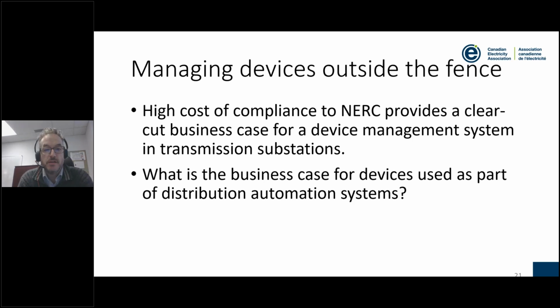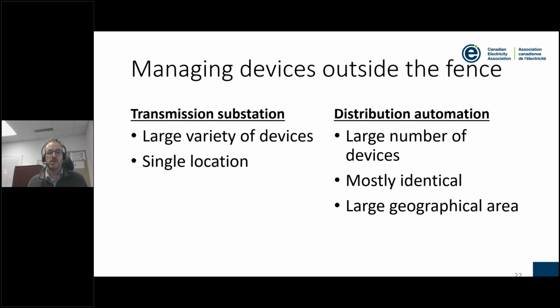Just the cost of trying to be compliant with NERC is a business case in itself for transmission substations. Typically, budgets associated with transmission substations are much higher than distribution, but is there still a business case for devices used in distribution and automation systems? Transmission substations have a large variety of devices but only a few locations, whereas distribution automation has a large number of devices that are mostly identical, such as capacitor bank controllers, voltage regulators, sensors, and other equipment. The challenge is that you have a much larger geographical area to cover.